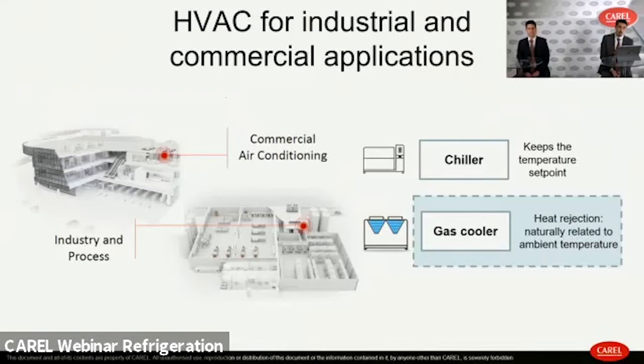As I mentioned, why both humidification and food retail refrigeration, and also HVAC? What we are analyzing here is CO2 as a refrigerant. It's a cross solution that's used both for refrigeration and HVAC. For HVAC, in both commercial applications and also industry and process ones, we most often have a chiller that keeps a temperature set point to cool down some water, while the heat is rejected to the ambient. So we have the above mentioned gas cooler, which is of course impacted by the air temperature of the ambient it's working in.